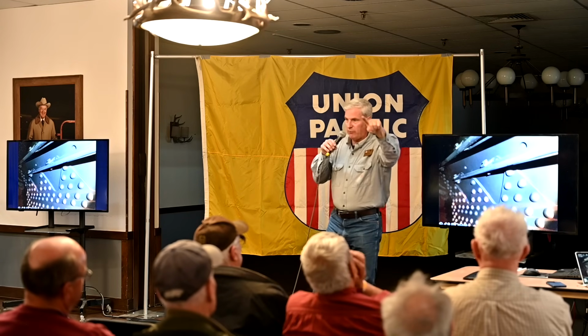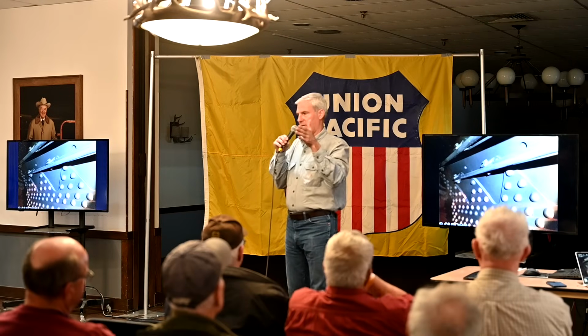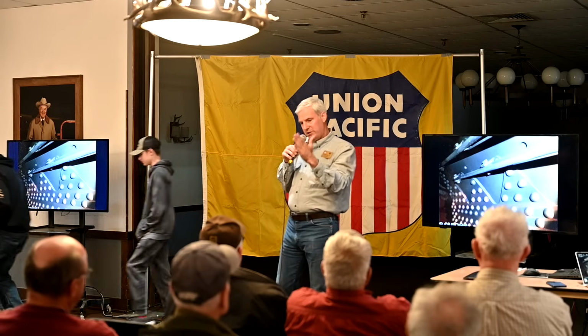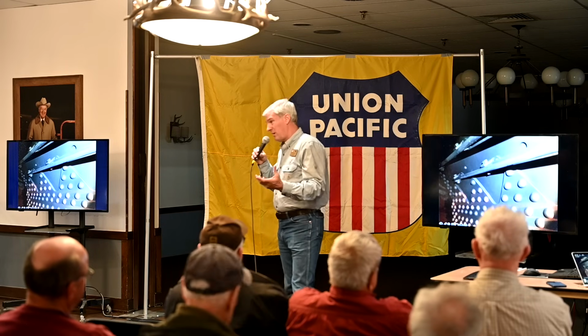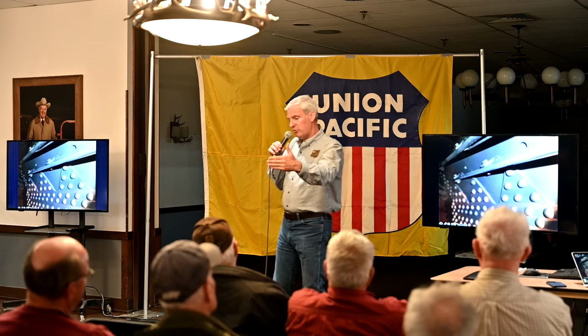Well, the steel itself, when it's rolled into a cylindrical plate, is self-supporting. And you've got these big reinforcing plates called liners, and they're riveted here, and that's how the boiler is held together. When you get to the firebox end, that is no longer a cylindrical structure, it's rectangular, and there are some radiuses in that structure. Now you've got 300 pounds per square inch of pressure, and if you do the calculation on the stay bolt loading, you're at like 7,400 pounds. This is a tremendous pressure that steam is exerting at all times. So that metal plate is held together with all those stay bolts.